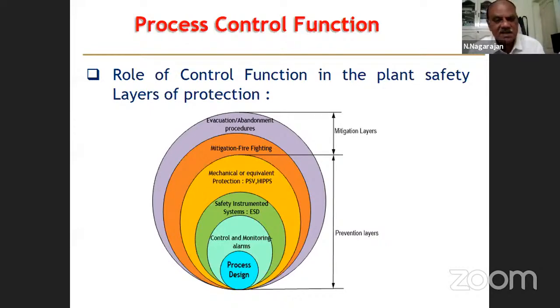We have safety layers, like in safety instrumentation, we have fire detectors, gas detectors, smoke detectors. Then they will activate the mitigation systems, that is the emergency shutdown system. And then mechanical devices are also used to take care of such pressure developments. One is the PSV, pressure safety valve. Most of you know, any pressure equipment will have a pressure safety valve, and it is a mechanical device. It is not activated by any signal from the safety layer. It is mechanically devised so that it will open when the set pressure is reached, and it will release the excess pressure to the flare system.